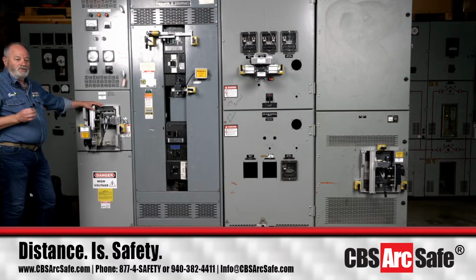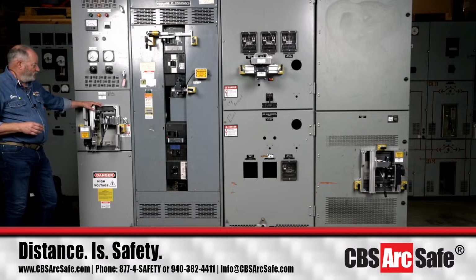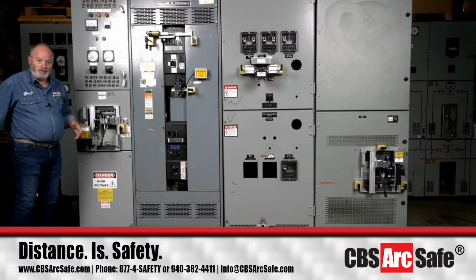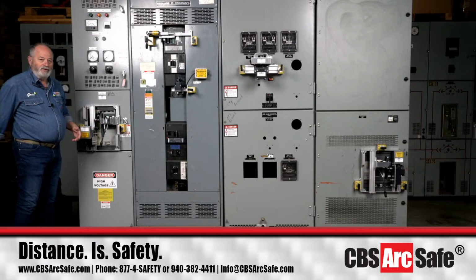One thing to also note is older breakers will show wear. I carried a Magnum DS breaker on my demonstration truck for 2 years, and initially it was 5 strokes, but over time, because it was the most worn Magnum DS breaker I know of, it went to 8, 9, and then 10. We finally had to replace the charging mechanism on the breaker for it to operate right again.